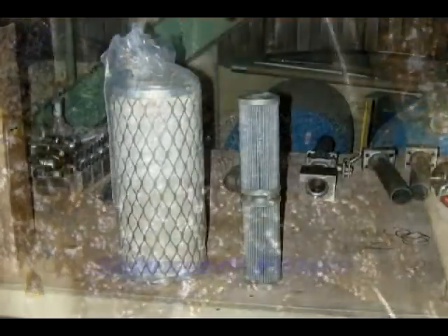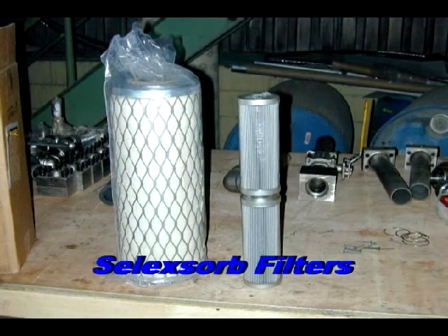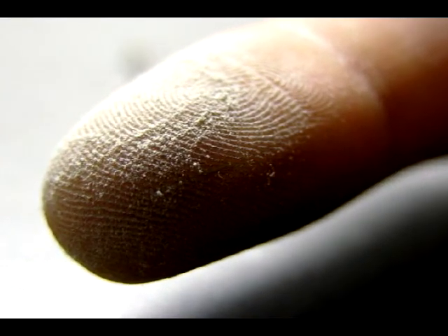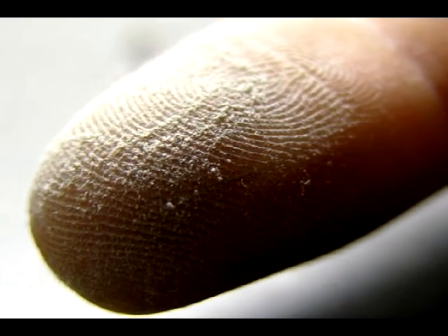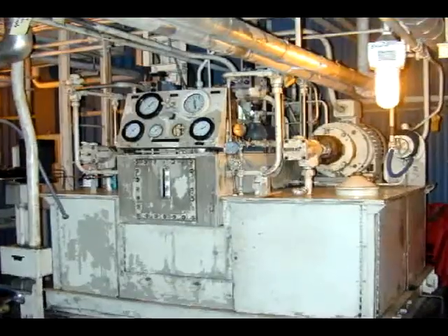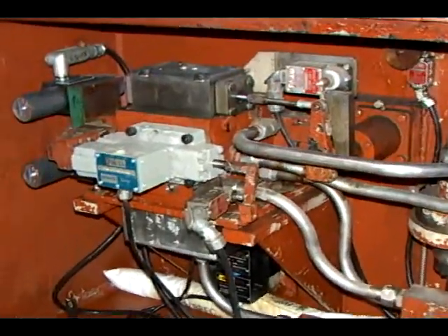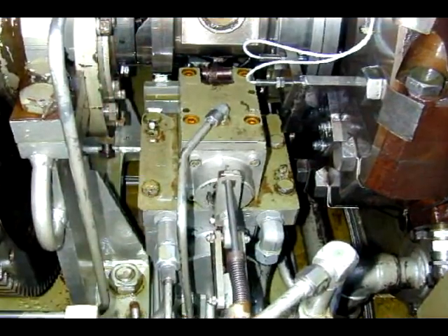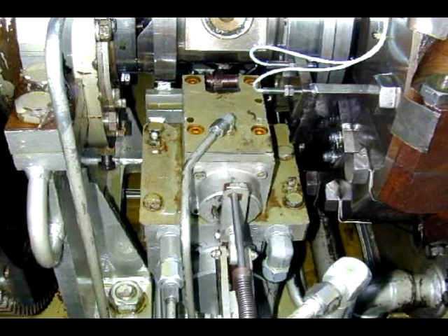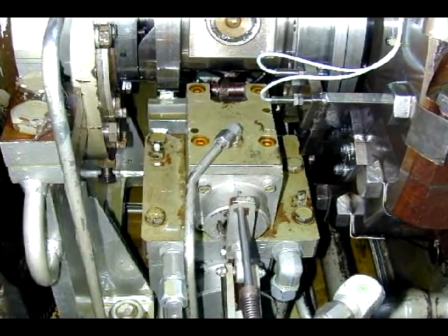In order to eliminate the release of metal salts and ultimately the formation of gels and varnish, select sorb filters were introduced about 20 years ago. Experience with select sorb filters indicates they have a tendency to release ultrafine particulates into the hydraulic fluid system that cannot be removed with standard filtration. Over time, these ultrafine particulates can cause silting to occur in mechanical components that are not routinely tested, resulting in a failed test due to a sticking valve.